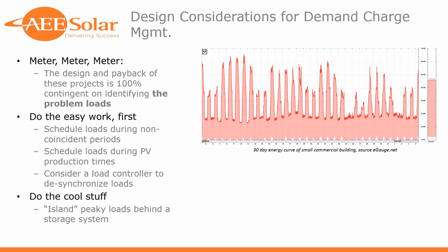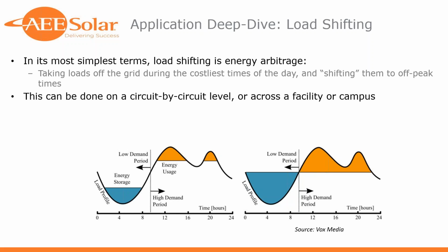We've worked with some customers and we've recommended that certain pumps, motors, et cetera, be put behind a storage system so that we're basically chopping the peak off of that load when it turns on. And it's perhaps best exemplified by this graph down here at the bottom. Basically what we're doing is using energy storage like a reservoir to draw from and bring down the peak on those loads. Think about it as a capacitor, really.